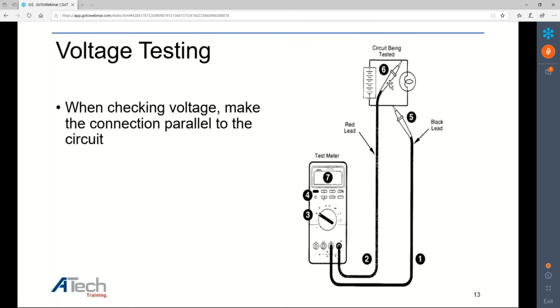Now, voltage checking, we're always going to check in parallel. Wherever I'm putting my black lead to ground, I'm going to check voltage up here. All I'm reading is the amount of voltage available at that point, and I'm going to measure it on my meter. I'm supplying a pathway to ground, bypassing everything. Since we have a really good meter with 10 mega ohms or more, that means I'm not going to affect the circuit.